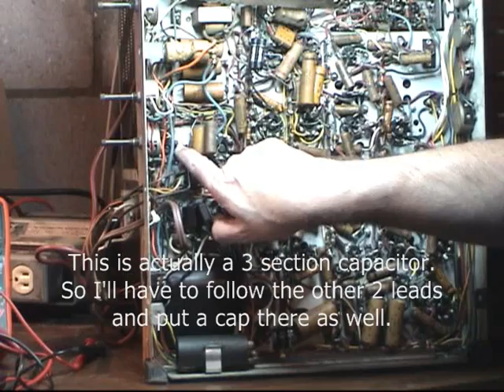I'll use the can connections here as a tie point, but we'll take this connection off so it'll be isolated. It'll break the contact off. You see, when I want to go replace this cap here, everything is grounded, so all I really need to do is follow where the wire is going. Say this one here, this yellow wire actually comes up to this point here. So I can just look on the terminal strip, either above it or below it. Okay, here's a ground connection here, so I could just stick the cap there without too much trouble. And it'll actually be where the power is being used, so it's actually a better place to put it. So, as a matter of fact, the cap that goes here is much smaller. It's only a 50 volt cap, so it won't even look this big. It'll be very, very small.